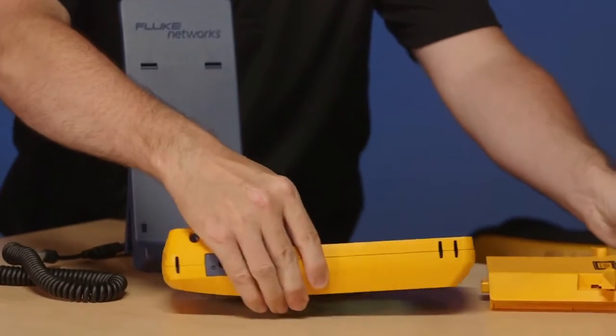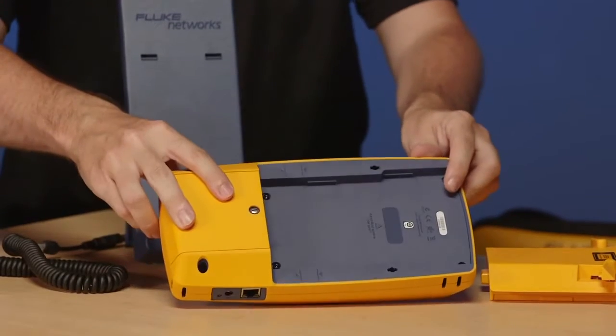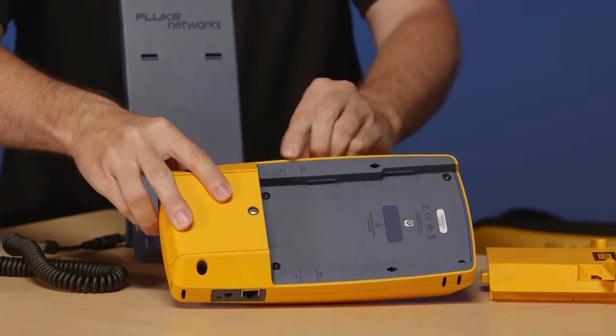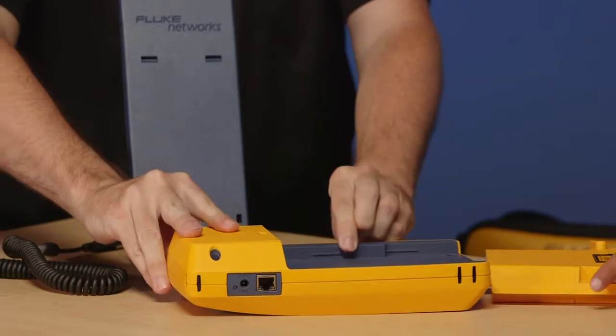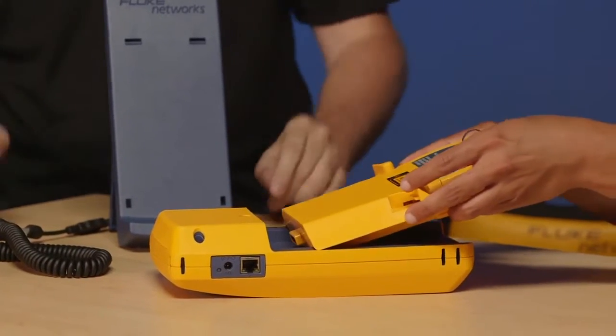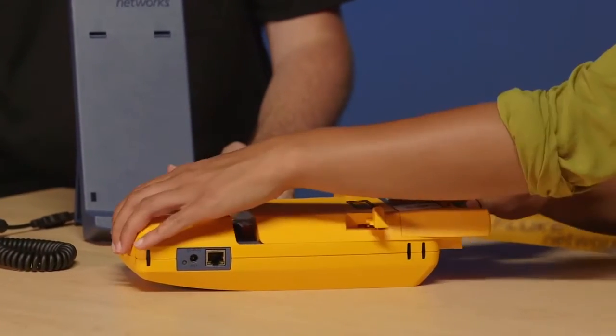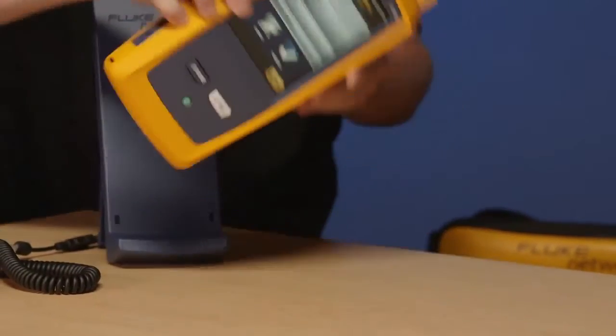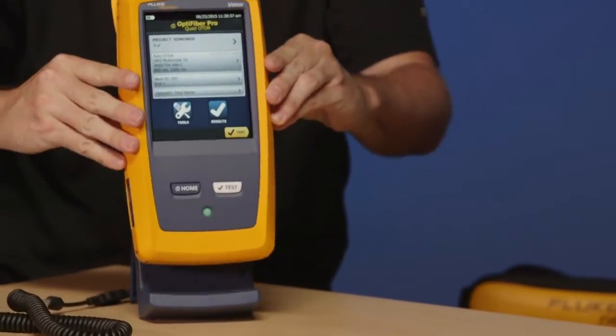Inserting a module is quite easy. When you look on the back of the tester, you'll see a couple of arrows. So Amanda's going to drop the module in, slot it in between those 2 arrows, push the instrument together, push the ears down, and now you've got a fully functioning OTDR.